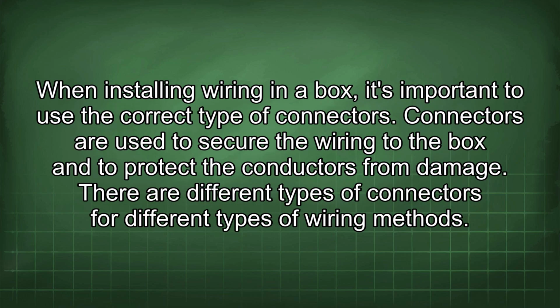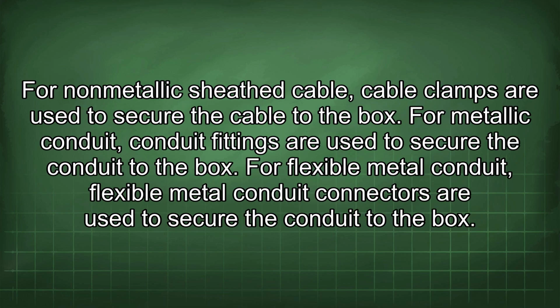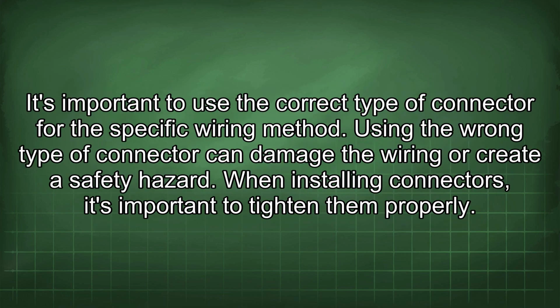When installing wiring in a box, it's important to use the correct type of connectors. Connectors are used to secure the wiring to the box and to protect the conductors from damage. There are different types of connectors for different types of wiring methods. For non-metallic sheath cable, cable clamps are used to secure the cable to the box. For metallic conduit, conduit fittings are used to secure the conduit to the box. For flexible metal conduit, connectors are used to secure the conduit to the box. It's important to use the correct type of connector for the specific wiring method. Using the wrong type of connector can damage the wiring or create a safety hazard.